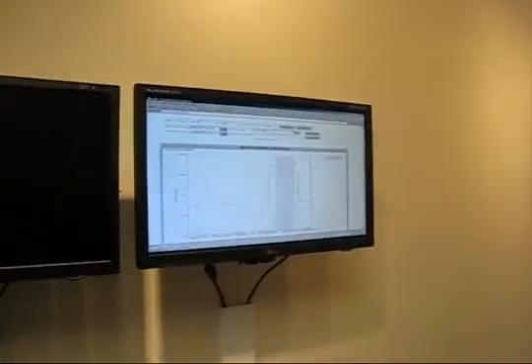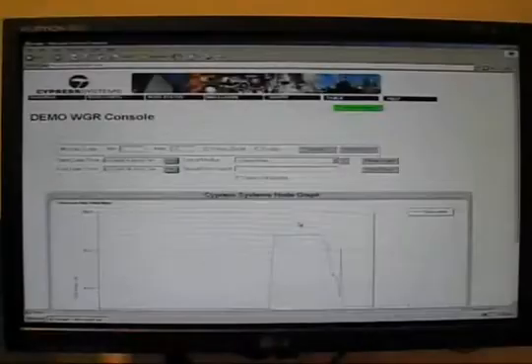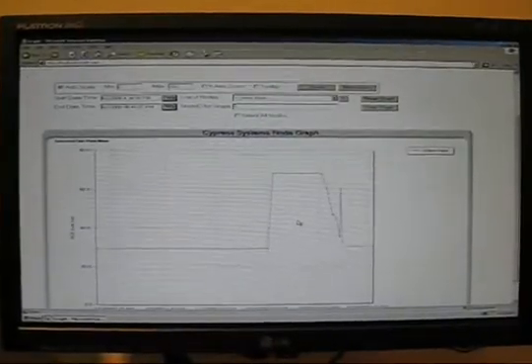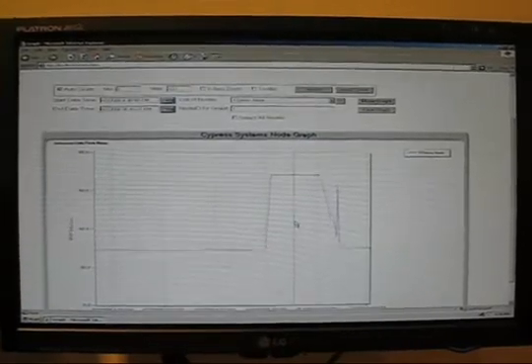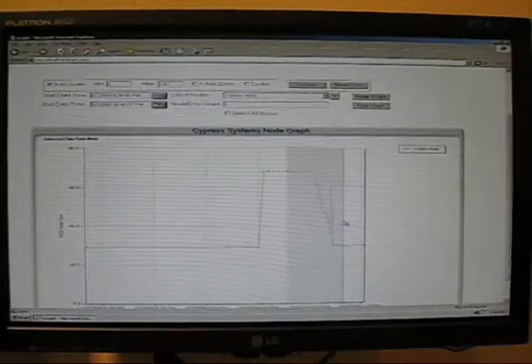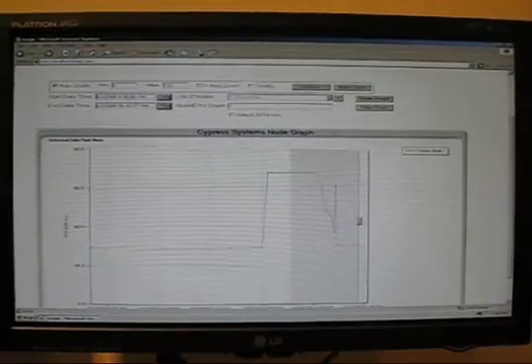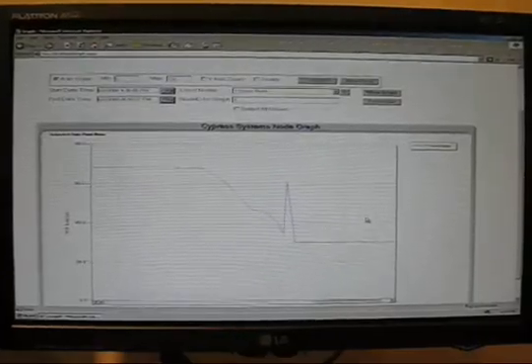Now the reading gets transmitted to a central server, which then allows the user to plot and look at alarms and history of the data, which is all included together with the system. You can select time intervals, you can expand to look at more resolution, set upper and lower alarm limits, and notify your cell phone if you have an excursion.